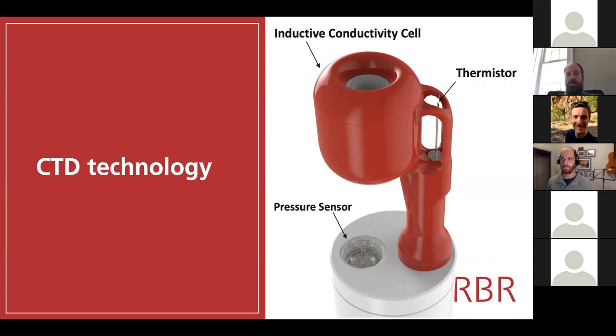by applying a voltage between two electrodes and seeing what current flows. And the fundamental way that an electrode-based conductivity cell works is exactly that. A voltage is applied between some electrodes, a current flows between those electrodes because of the conductive fluid that's between them. And either you apply a constant current or a constant voltage, but by measuring the opposite variable, you can derive resistance, resistivity, once you know the cell constant, which is a geometric factor.